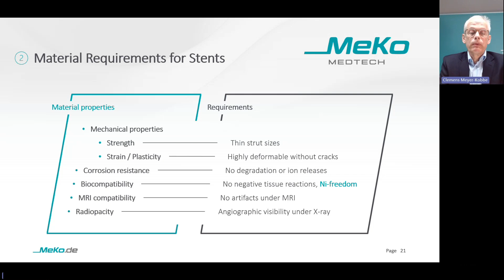With the mechanical properties, we want to ensure thin strut sizes, and the stent should be highly deformable without cracks. Corrosion resistance. This means we don't want any degradation or ion releases. We also don't want negative tissue reactions, which can only be ensured for all patients if the material is nickel-free. And we don't want artifacts under the magnetic resonance imaging. And finally, the cardiologists, they want to have a good visibility on the angiographic or under X-ray. When we were developing the nickel-free alloy, we had to pay attention to these 5 characteristics. Finally, we succeeded to develop a suitable nickel-free alloy and called the material Vasculoy.